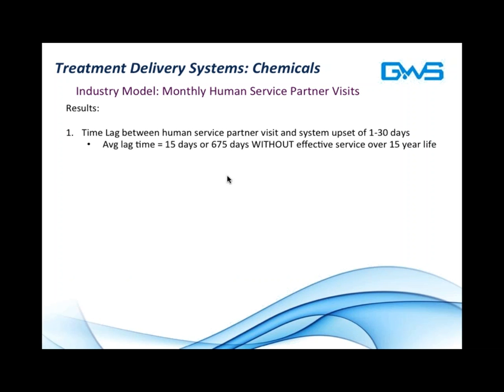Let's look at the results from that. There's a significant lag time between human service partner visits and the system upsets that occur on average 3 times a year for a given cooling tower, between 1 and 30 days, which is an average lag time of 15 days. Over a 15-year life of the tower, you're talking about 675 days without effective service. That's almost 2 years of a 15-year tower lifespan to effectively have the tower out of calibration. Again, this is not necessarily the fault of the chemical service provider, although sometimes mistakes happen there. It's really the fault of the operating conditions of the cooling tower, something going wrong downstream of the system.